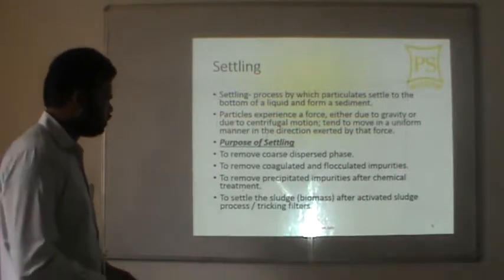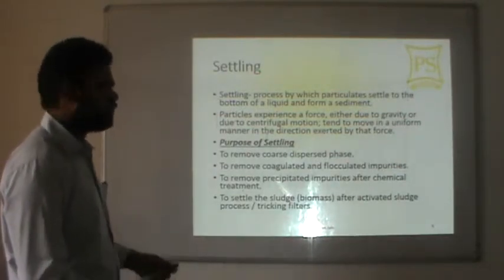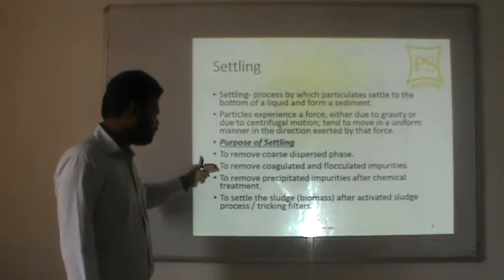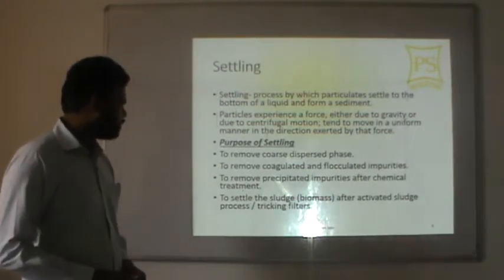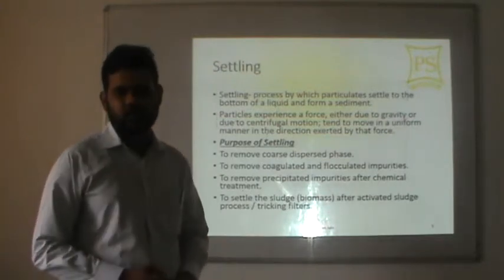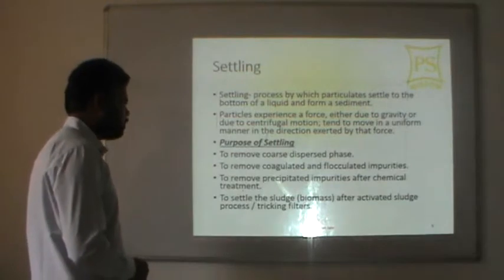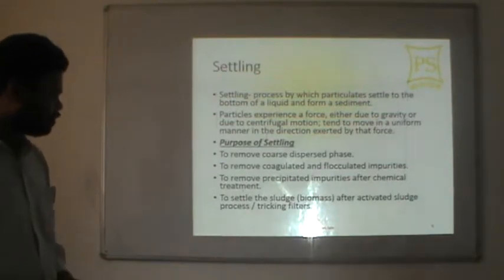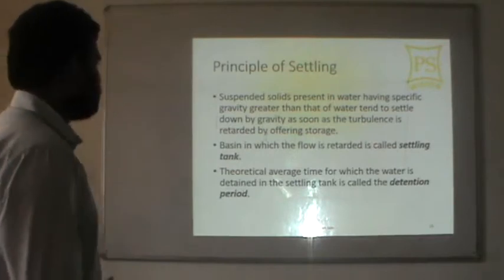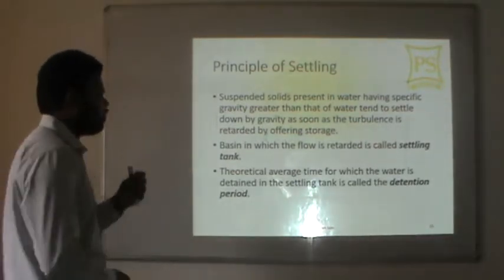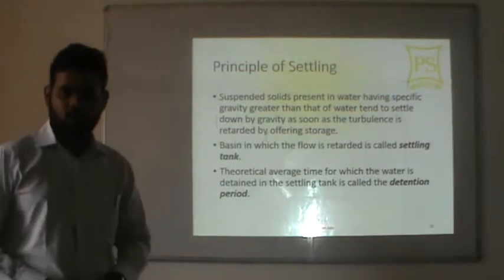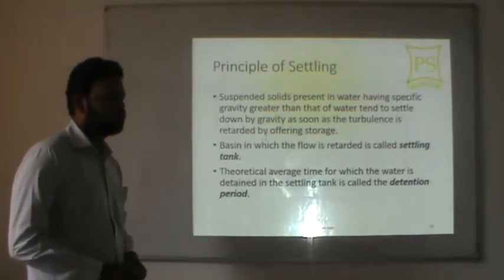The purposes of settling are: to remove coarse dispersed phase (Type 1 settling), to remove coagulated and flocculated impurities (Type 2 settling), to remove precipitated impurities after chemical treatment, and to settle biomass after activated sludge process. The principle is that suspended solids with specific gravity greater than water (greater than 1) settle down by gravity once turbulence is reduced.